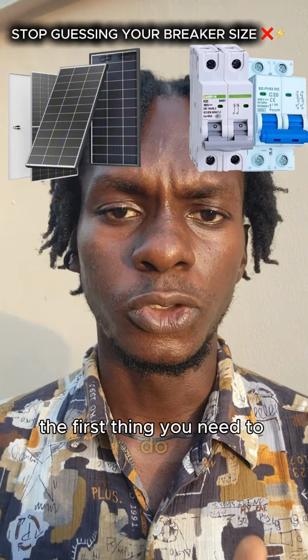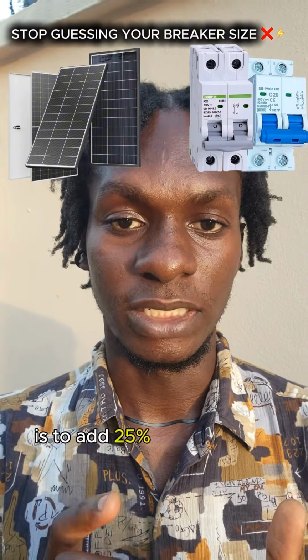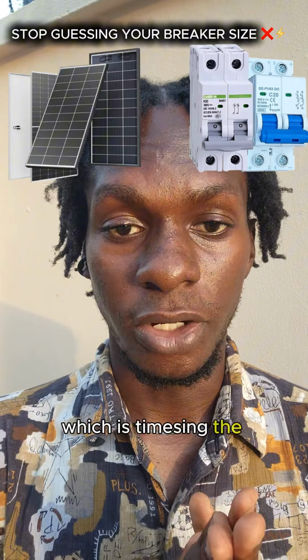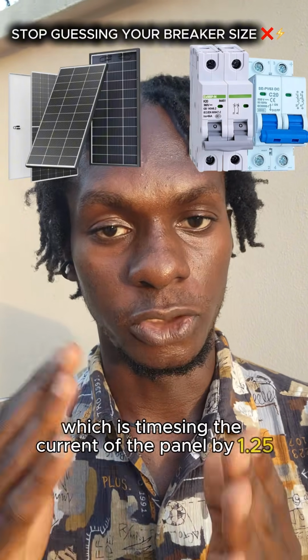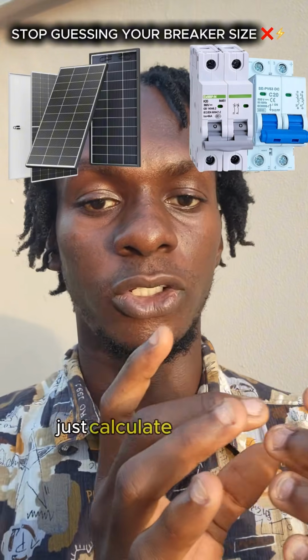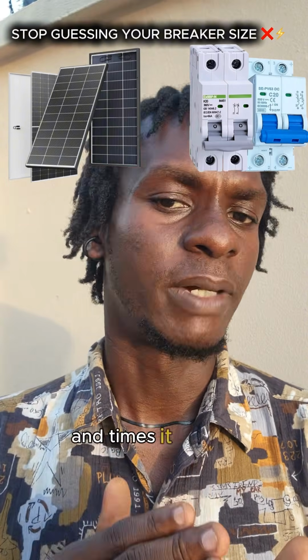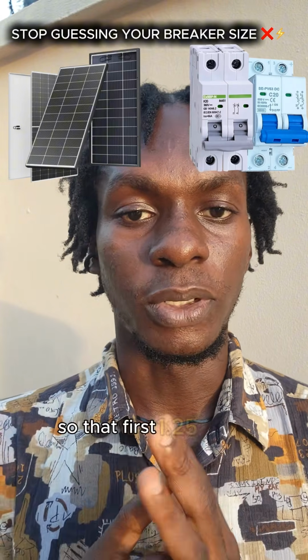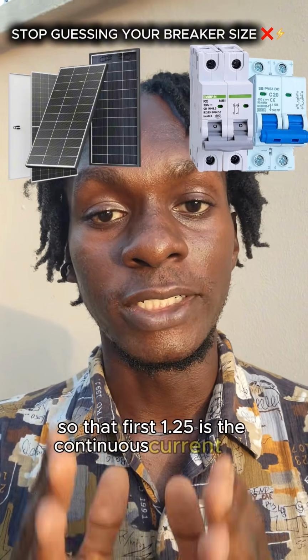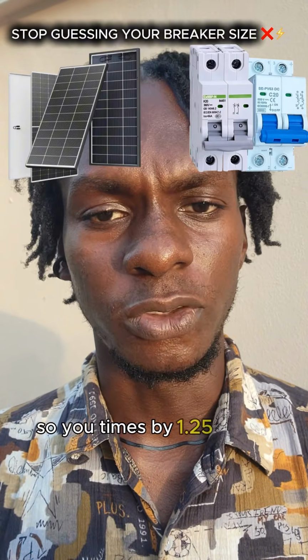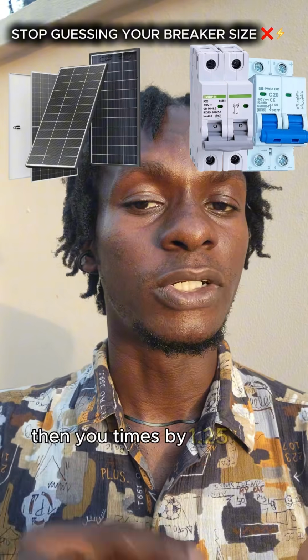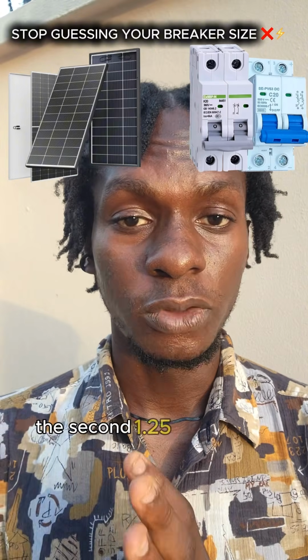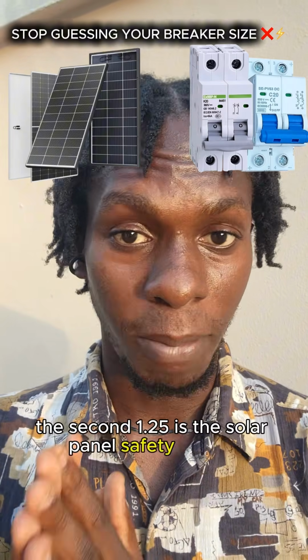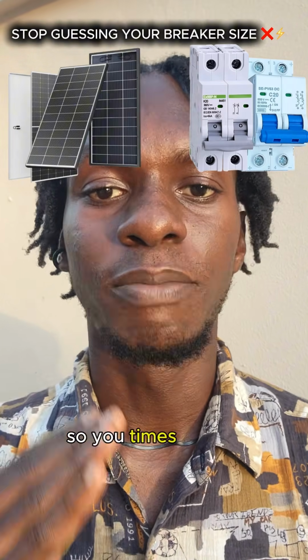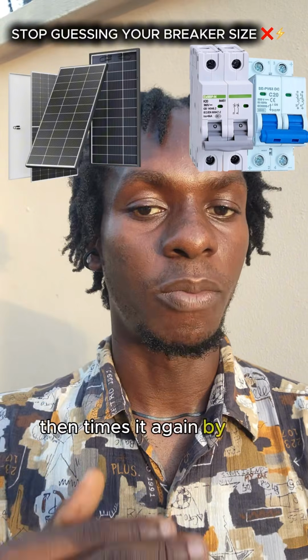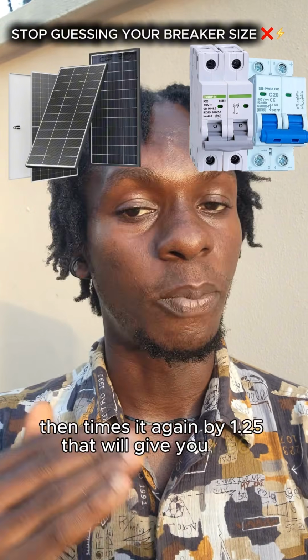The first thing you need to do is to add 25% of the current, which is timesing the current of the panel by 1.25. If you have multiple panels, just calculate the total current of the panels and times it by 1.25. So that first 1.25 is the continuous current rule. So you times by 1.25, which is 25%. Then you times by 1.25 again. The second 1.25 is the solar panel safety margin. So you times by 1.25, then times it again by 1.25. That will give you 1.56.